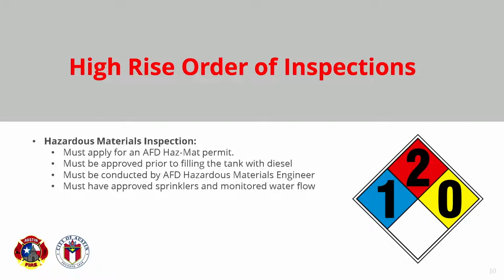So the hazmat inspection, the one I'm talking about right here, is to put diesel into the generator. This is one of those scenarios where these inspections have to take place in order. You have to get your hazmat inspection so you can put diesel into your generator. You have to have diesel for your generator in order to get your load bank test. You have to have your load bank test before we will schedule your fire pump test. You have to have your fire pump test before we'll schedule your PRV testing or your standpipe flow test.